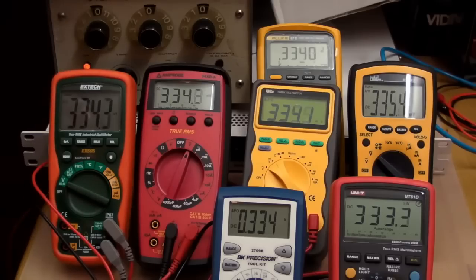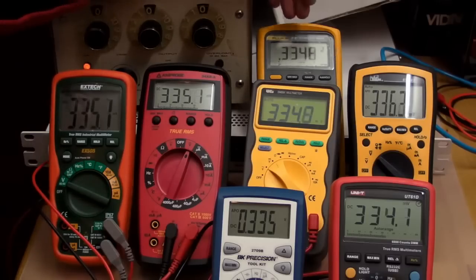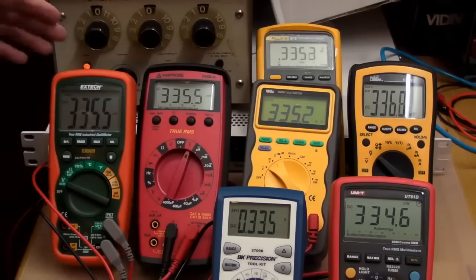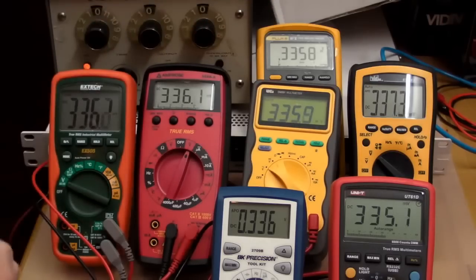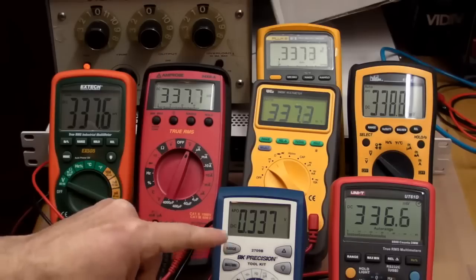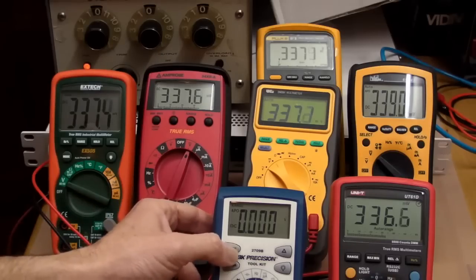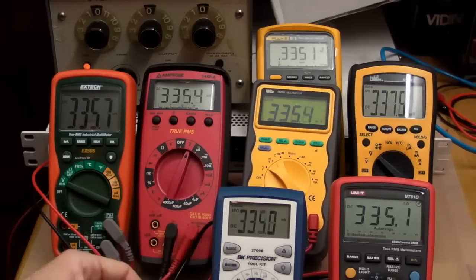Let's try the 330 millivolt range. 335 millivolts on the Fluke, and they're all pretty darn close, within spec, no problems at all. The BK Precision looks like it hasn't ranged down, so we'll take that into manual range.